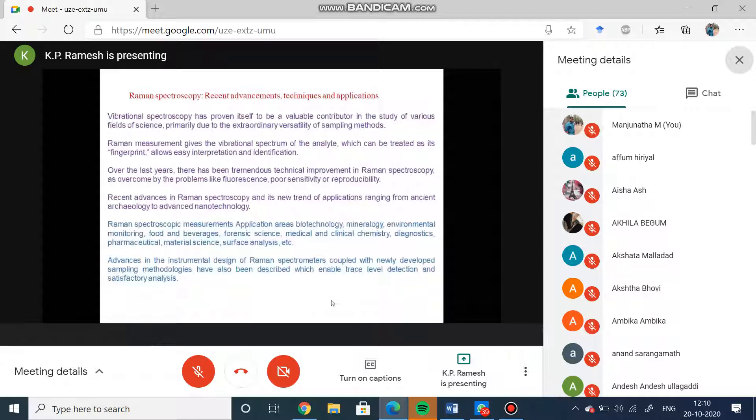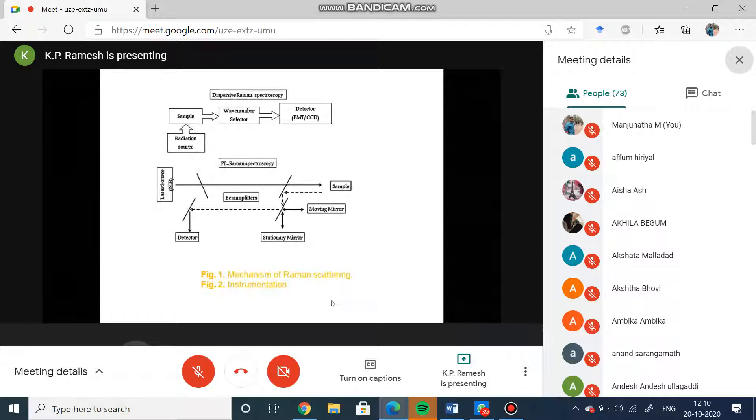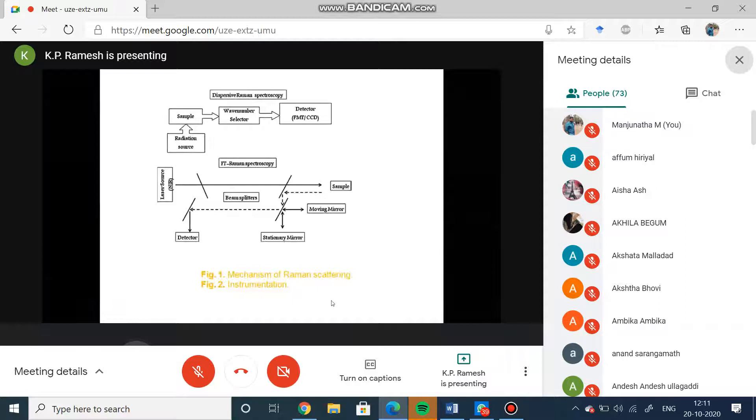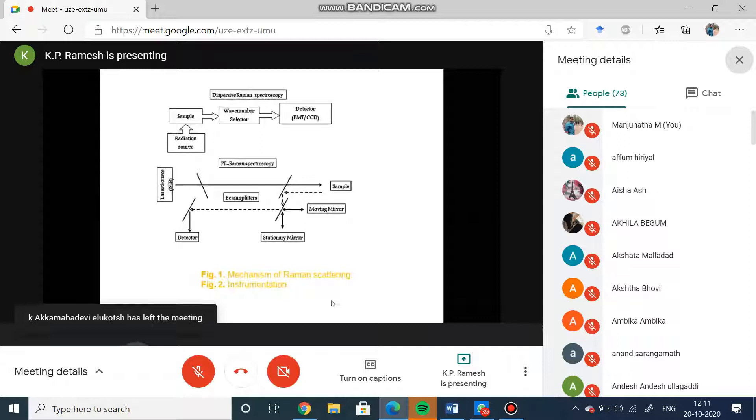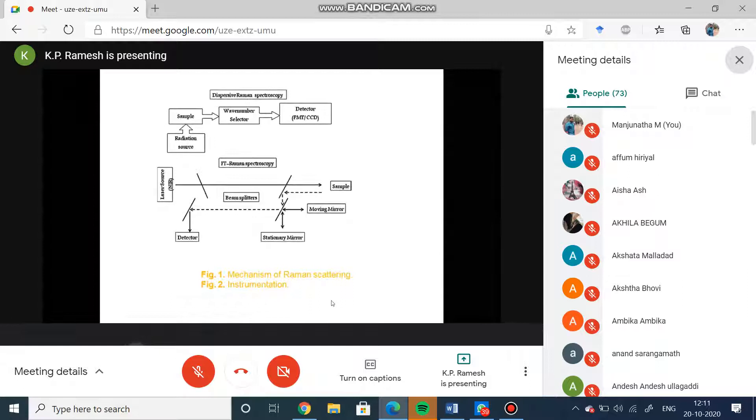This is the modern Raman spectrometer what you see. You have a radiation source, it goes to the sample, then you have a wave number selector, and the output will go to the photomultiplier tube or CCD camera. This is how you can do dispersive Raman spectroscopy. FT Raman spectroscopy consists of a laser source which goes to the sample, then using beam splitters you split the beams, then you have two mirrors - one is moving mirror and the stationary mirror. The beam coming from the sample and the beam coming from the source both will be incident, they get mixed here, then wavelength analyzed and that goes to the detector.